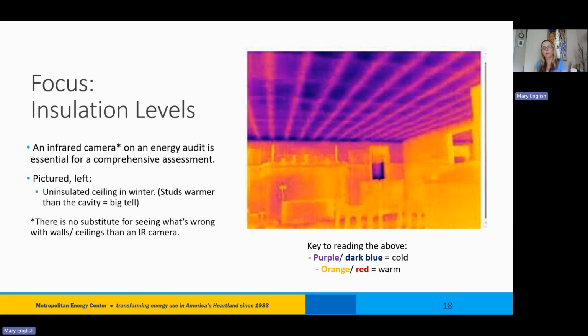If it were insulated, it would be reversed. You would see the ceiling joists as colder than the cavities, but because the cavities are colder than the framing, those joists, it means that it's uninsulated. There's really no substitute for seeing into walls and ceilings than an infrared camera. If you suspect that your building is mostly uninsulated, it might be really worth it to get a level 2 assessment, or at least somebody just to come in and do an infrared scan. You have to do it when the temperature difference is at least 20 degrees between inside and outside. So infrared doesn't work very well in the moderate spring and falls in this area.